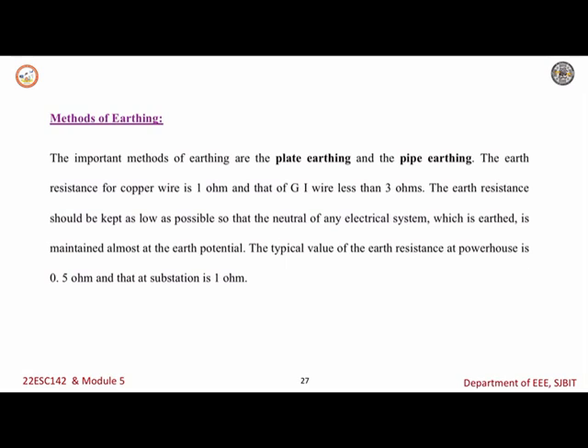The earth resistance should be kept as low as possible so that the neutral of any electrical system which should be earthed is maintained almost at earth potential. The earth resistance at powerhouses is around 0.5 ohm, and at substations it should be 1 ohm, because at the powerhouse we generate power at a very large rating and the current flowing is very high. That's why we should maintain the earth resistance at only 0.5 ohms at the powerhouse, and near the substation at 0.1 ohm.